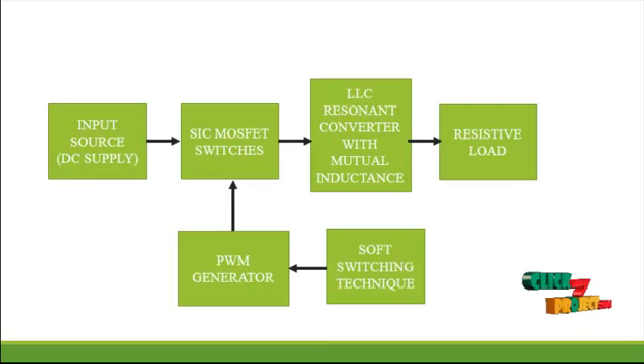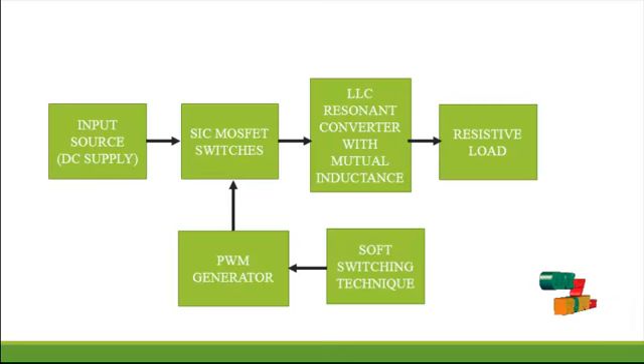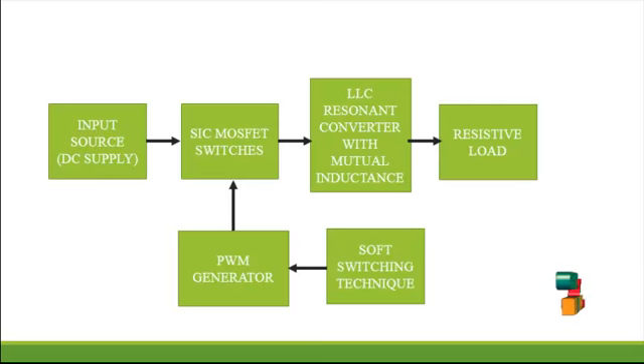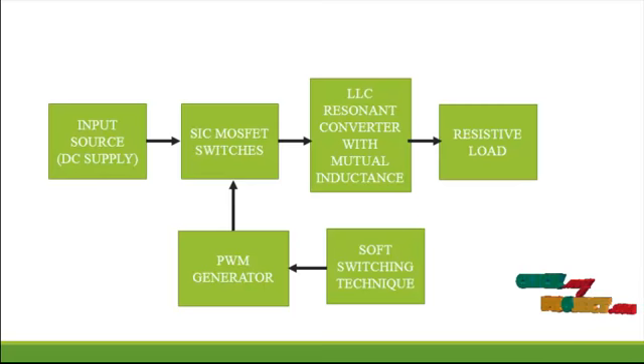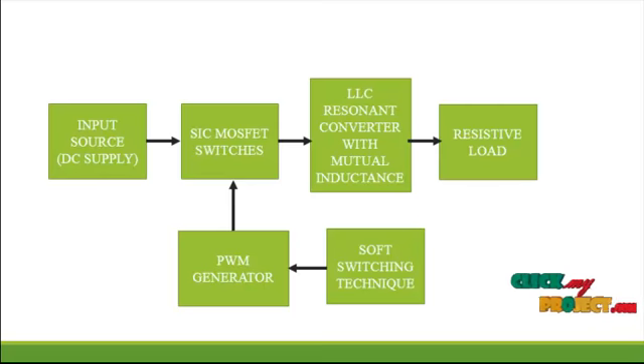The PWM generator supports many PWM techniques, and here we use the soft switching technique. The main objective of soft switching is to reduce switching losses and switching stresses, which increases the converter lifespan. The resonant network consists of a capacitor, leakage inductance, and the magnetizing inductance of the transformer.